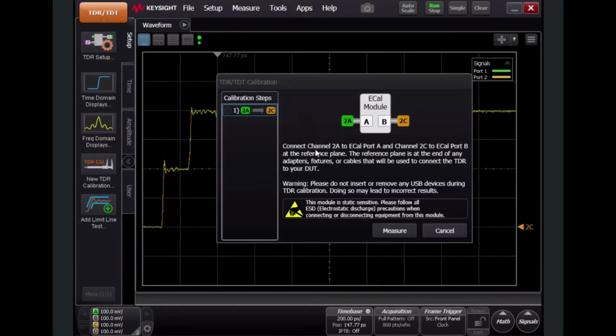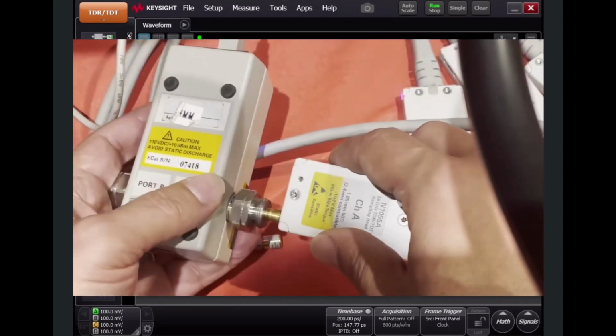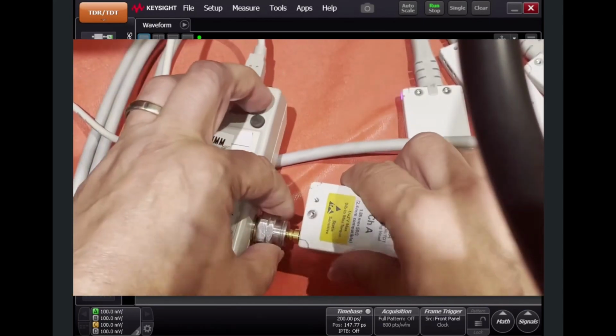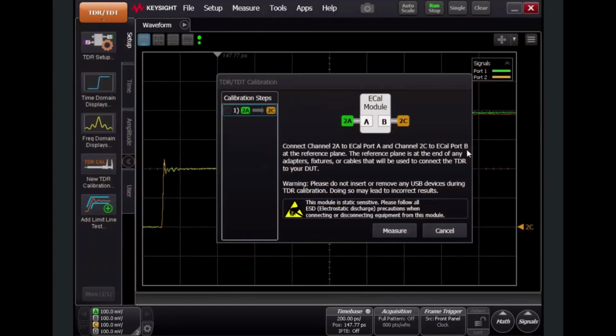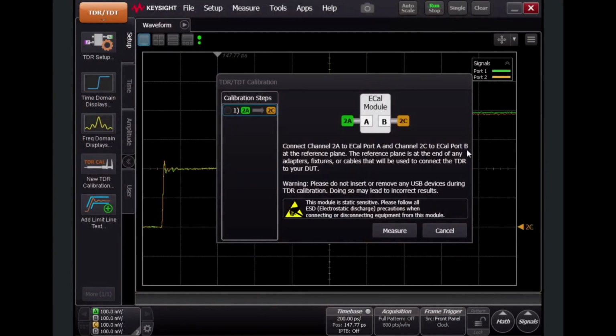I'm going to start the wizard. Connect channel 2A to the Ecal. A few things to remember. Make sure you're using the torque wrench, and most importantly, these are static sensitive. I have an anti-static mat, I have a wrist strap, it's also connected to ground. Okay, I have them connected, 2A and 2C are connected. Let's do a measurement.